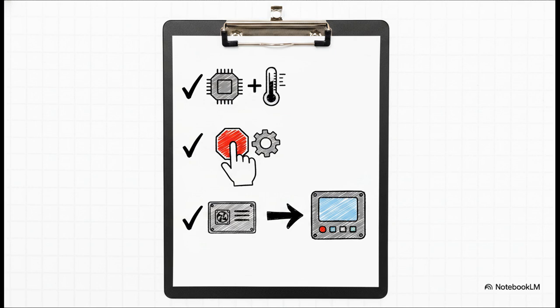And finally, Section 5, key takeaways to protect your equipment. To wrap things up, let's distill your biggest takeaways for today. First, understand the difference between the mathematical I²T model and physical PTC probes. Remember that on the ATV320, you can and definitely should use both if your motor has probes. Second, always navigate to the FLT menu when the drive is stopped to set your safety boundaries. And lastly, the most common and destructive mistake in the industry. Never ever leave the ITH parameter at the default drive rating. Always punch in your exact motor nameplate current before you ever hit run.